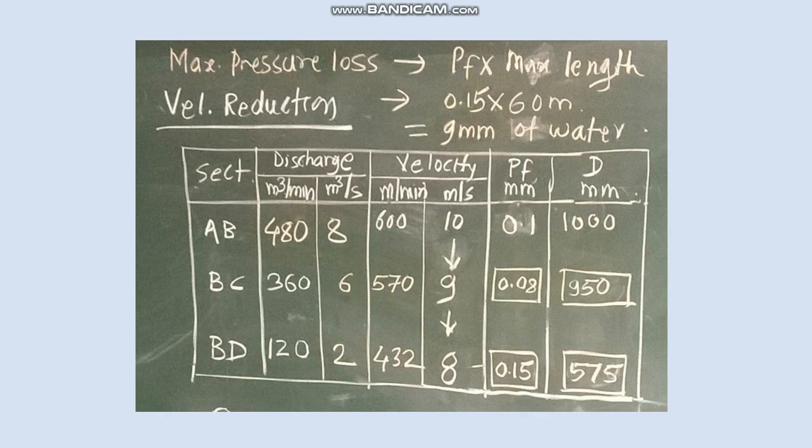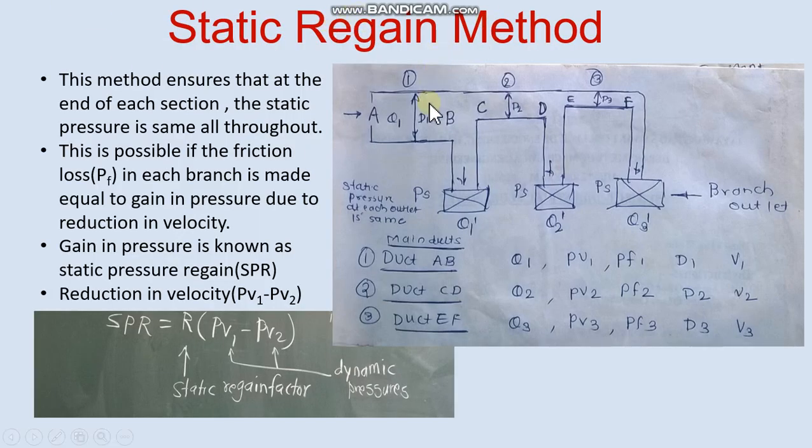The third method is static regain method. This method ensures that at the end of each section the static pressure is same. So PS, static pressure, is same. So how it is possible? It is possible if the friction loss, that is PF in each branch, is made equal to gain in pressure.